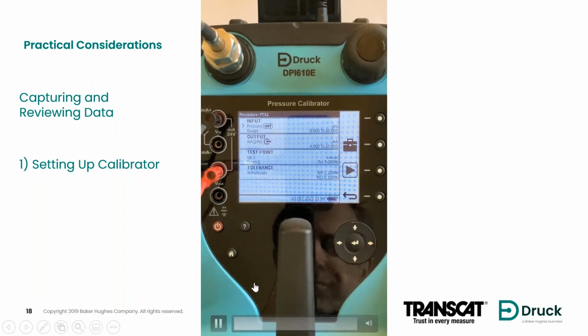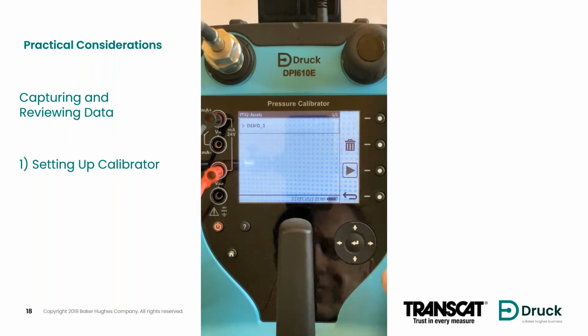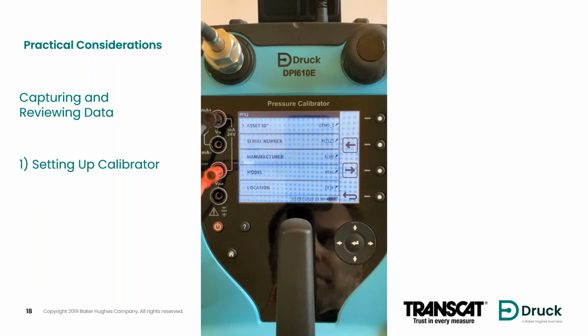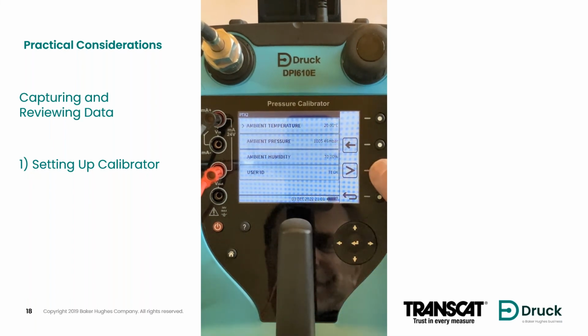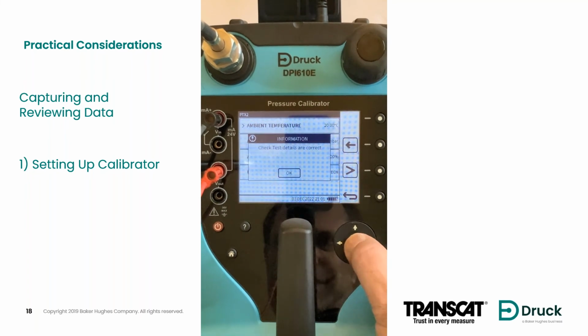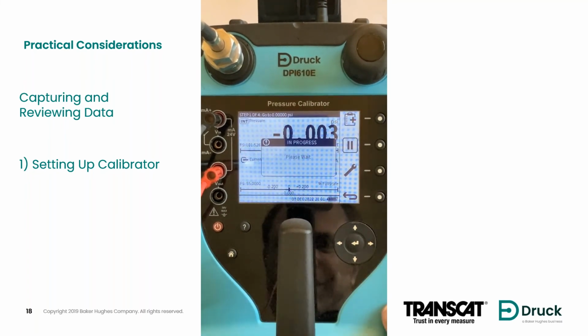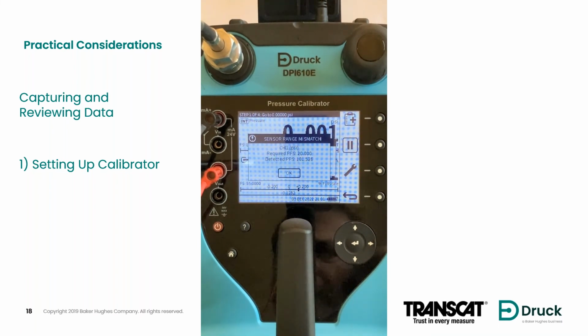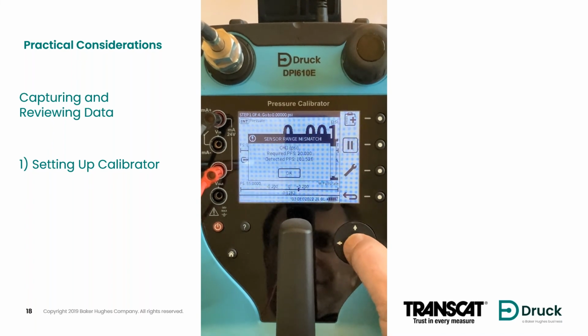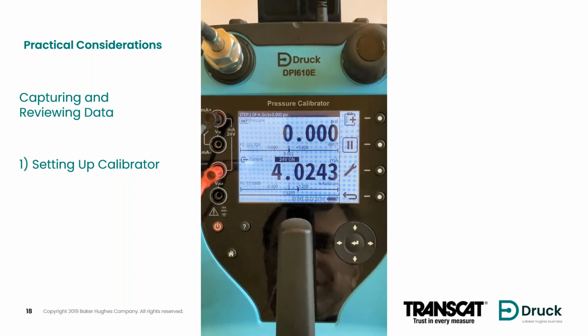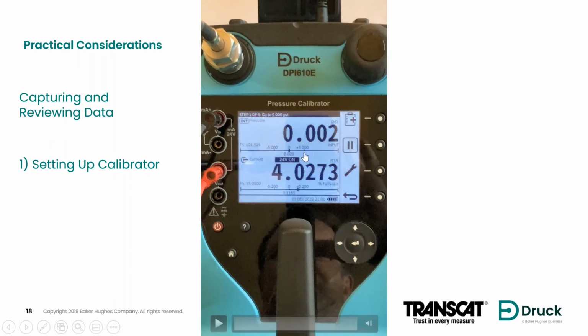The thing that I wanted to highlight once we get to the actual calibration screen, which we'll do in just a second here, is that not only does it give you the ability to capture those data points, it actually shows you your tolerance banding for the pass fail and the adjustment that you defined in the procedure. So again, it gives you actual real-time indication of whether a point's in tolerance or not. Some of you may be math whizzes. I'm not. You might be able to do that calculation on the fly in your head. I can't do that. I think the error banding or tolerance down at the bottom of the screen that you see there is a helpful tool to have. So that's the setup of the documenting portion.